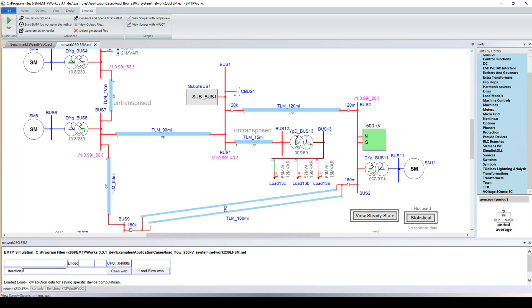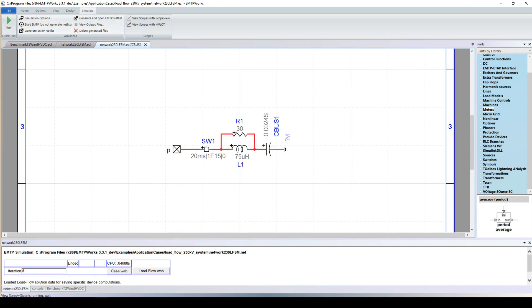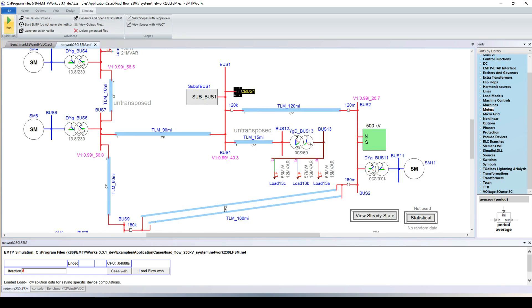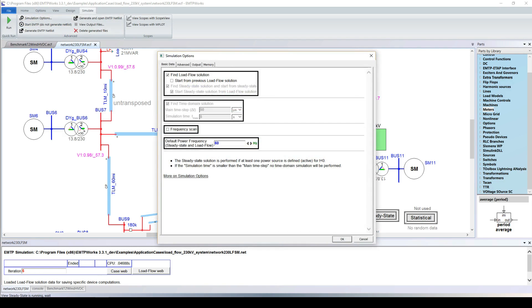Now, what happens when we switch the capacitor bank? It's very easy — we can simulate that in the time domain without changing tools. Instead of having the capacitor bank connected in steady state, we connect it at a certain time during the simulation, for example 20 milliseconds. We run the load flow again with the capacitor bank disconnected, going back to 0.96 PU, and then without any effort we change the simulation type from load flow to time domain.